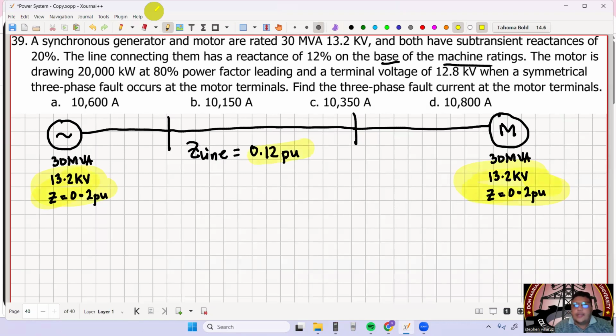So the motor is drawing - naka-unload siya - 20,000 kilowatts at yung power factor natin ay 0.8, with a terminal voltage of 12.8 kV. So meaning on load tayo, when a symmetrical three-phase fault occurs at the motor.